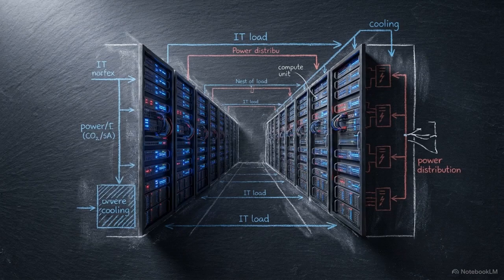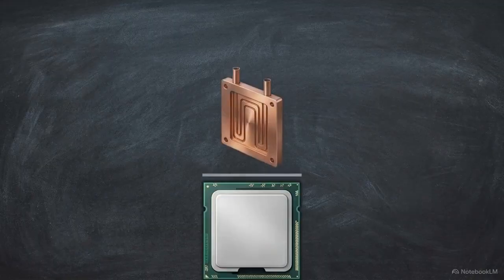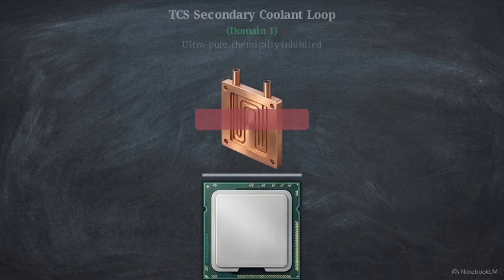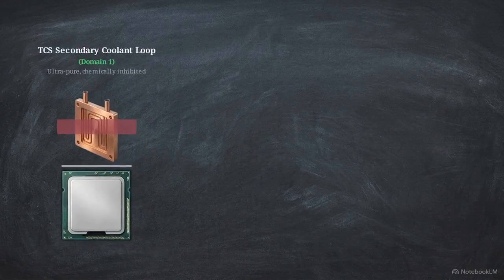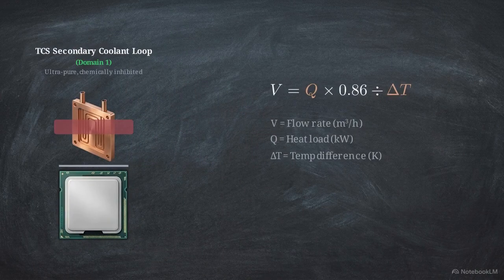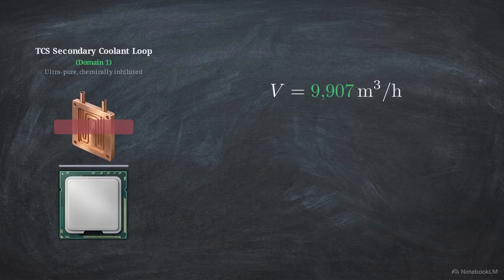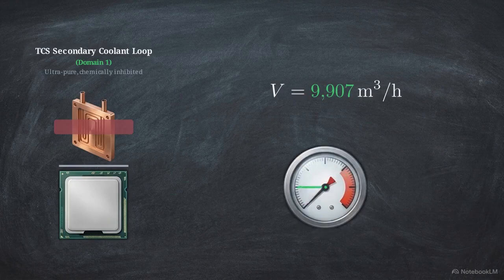For this 144 megawatt deployment, 80% of the IT load, or 115.2 megawatts, is captured directly at the chip via liquid cooling. A direct-to-chip cold plate is mounted to the high-power package. Heat moves from the silicon into the liquid flowing through microchannels. The heat transfer formula dictates that dividing the 115.2 megawatt load by a 10 Kelvin difference circulates exactly 9,907 cubic meters of fluid every hour.